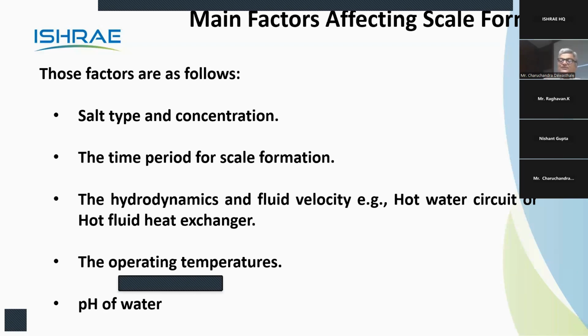Now, using the same analogy in heat exchangers, the velocity suddenly drops, going from say a 3-inch pipe into an area about 1 meter in diameter. So the velocity reduces, the flow gets divided, and the tendency to settle down at these low flow rates is higher in the condenser. So the condenser will get choked.